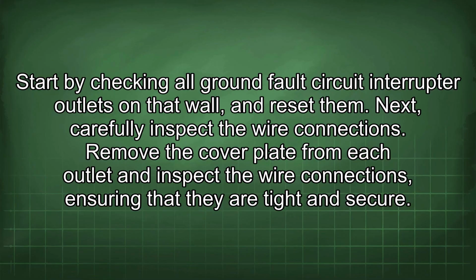Start by checking all ground fault circuit interrupter outlets on that wall and reset them. Next, carefully inspect the wire connections. Remove the cover plate from each outlet and inspect the wire connections, ensuring that they are tight and secure.